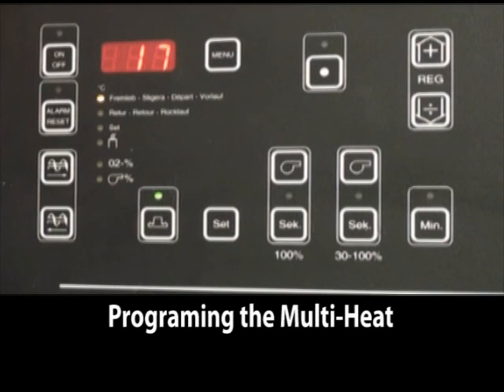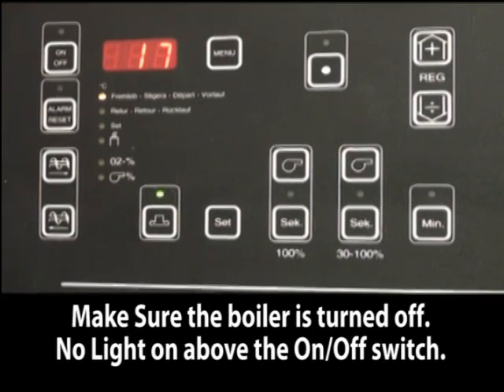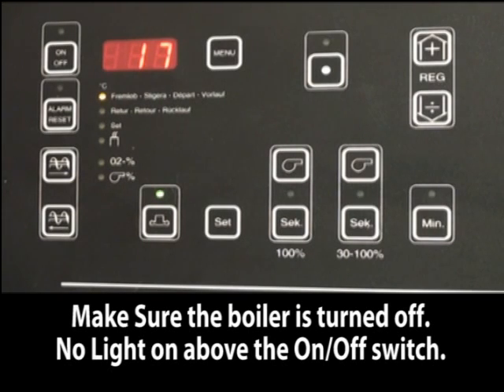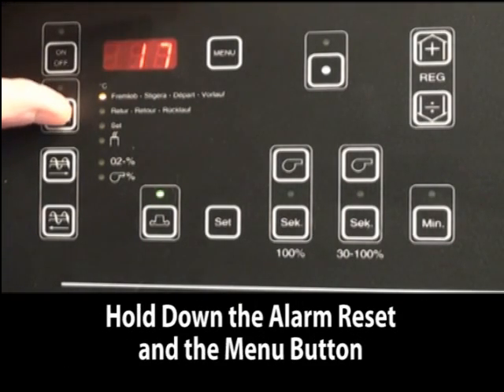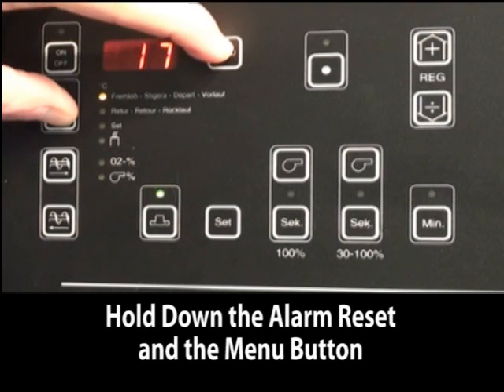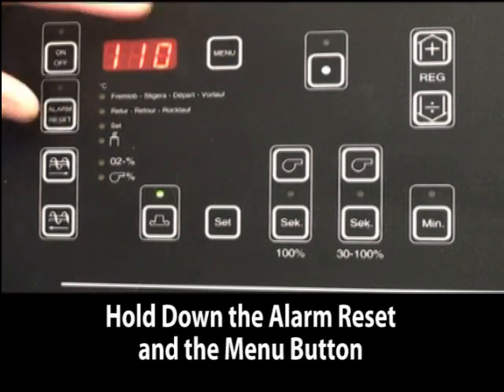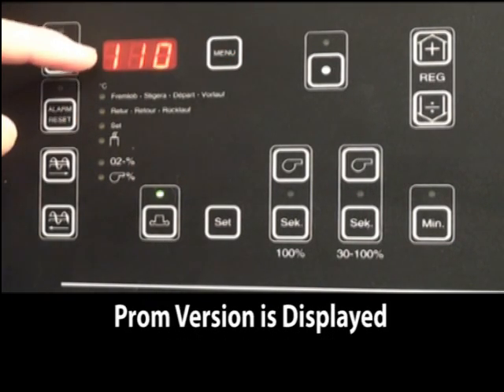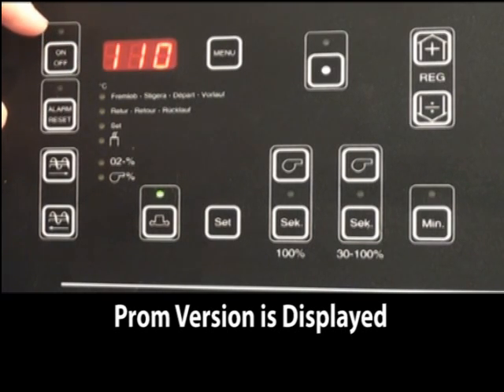Before you start the boiler for the first time, there is some background programming that needs to be done. To access the first layer of programming, hold down the alarm reset and the menu button at the same time until the PROM version is shown. This can be anything from version 107 through version 110.